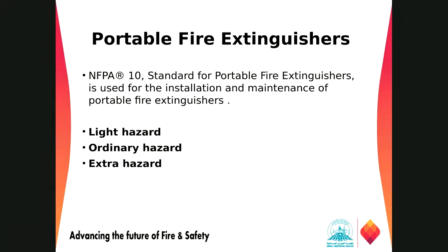Then as for NFPA, which is the standard for portable fire extinguishers, we have three different hazard classifications: light hazard, ordinary hazard, and extra hazard, right? The light hazard is where the amount of class A and class B combustibles is very minor. Those areas include classrooms, churches, assembly halls, residential halls, offices, and so on.